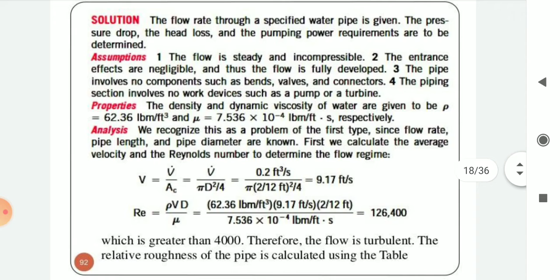The relative roughness of the pipe is calculated using the table. E/D = 0.000007 / (2/12 feet), which is equal to 0.000042. The friction factor corresponding to this relative roughness and the Reynolds number can be determined from the Moody chart. To avoid any reading error, we determine f from the Colebrook equation.